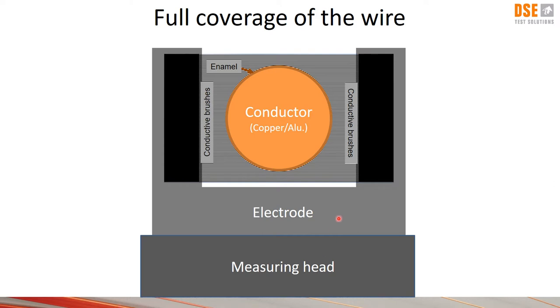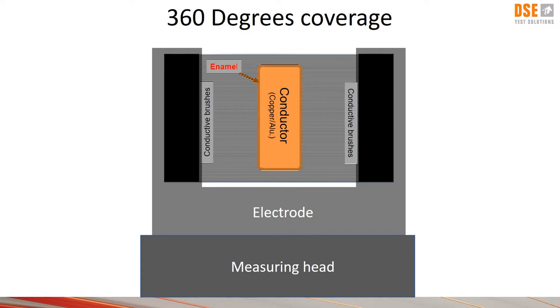As mentioned we use a set of brushes to obtain the test zone of 360 degrees around the wire. The first model is the standard model which is able to handle wire dimensions from 5 microns up to 2.5 mm. The second model is for heavier wire and has a dimension range from 0.5 to 26 mm. Note the brushes are covering also the corners which can be a problem to achieve in other systems.